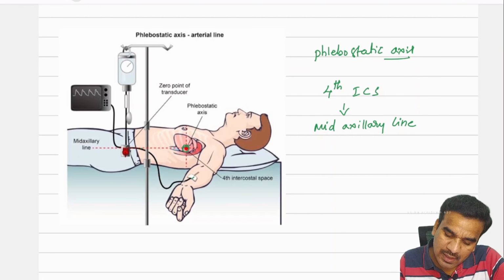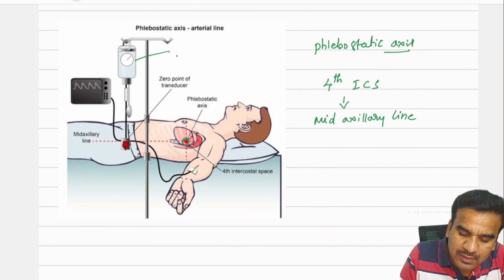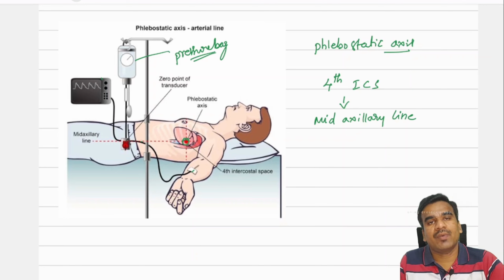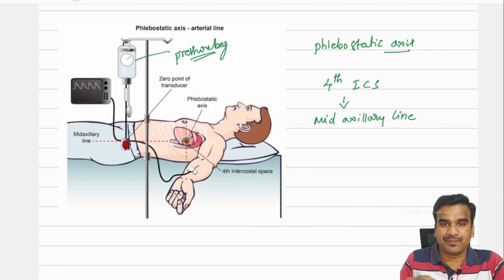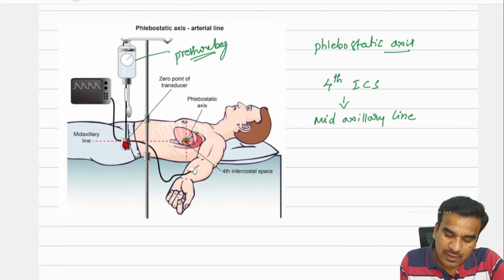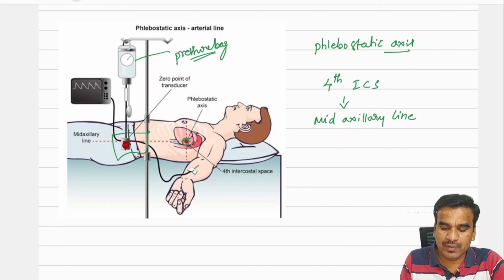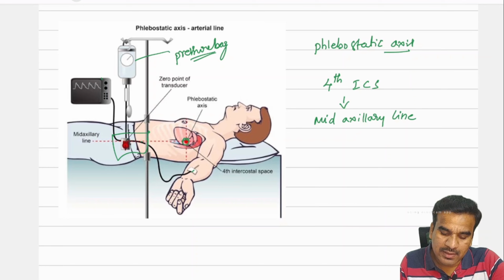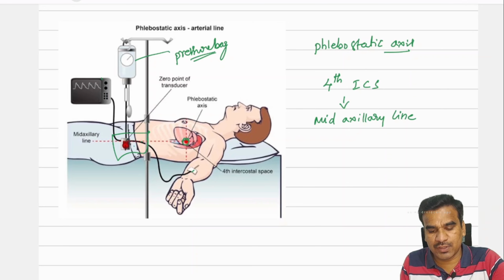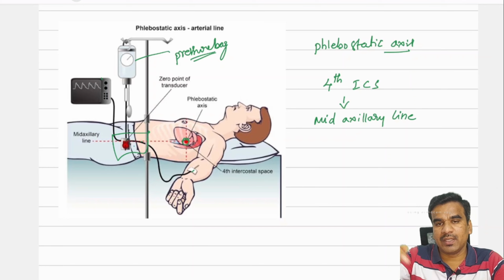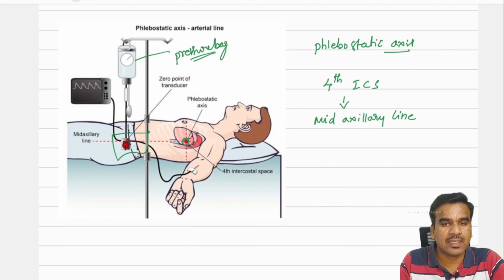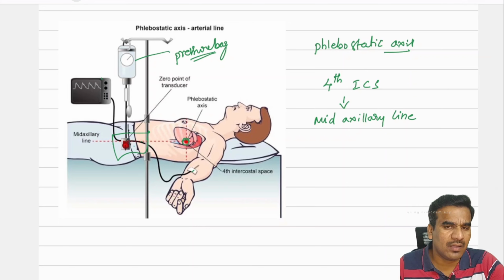So this is the arterial line, this is the monitor, and this is the pressure bag. Why are we using the pressure bag for the arterial BP? To prevent the backflow; it will push the blood inside. Also the transducer will be here, and we are fixing the transducer here. Both should be in a line: the transducer, the mid axillary line, the phlebostatic axis, and the hand in the same position. The patient should lie down supine. Then we do the zeroing of the arterial line. Those working in ICU settings might know how to zero the arterial line.